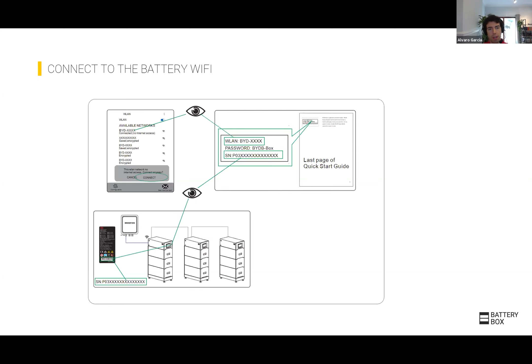The only thing we recommend is that you download the latest firmware before you go to site. This is because sometimes you might not have the best internet when you're down in a basement or in the place that a battery will be installed. So make sure before going to site to download the battery firmware. And also very important to do this every time, because there might have been an update from the last installation you did to this new installation. So make sure, it just takes a second, download the latest firmware. So when you get to site, you can connect to the battery Wi-Fi and update the battery.